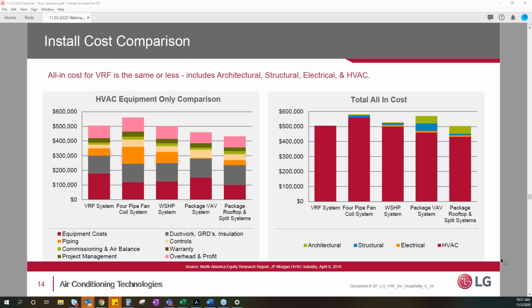And cost. Well, the equipment side of VRF is a lot more expensive, very comparable, let's say, to a water source. The overall installed cost is typically less than a 4-pipe fan coil, very similar to water source, a little bit more than you would have with the VAV system. VAVs are kind of an older technology, very inefficient. And then again, we have our packaged rooftops and split systems.